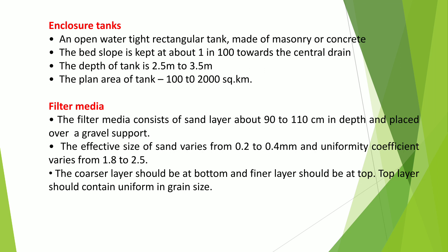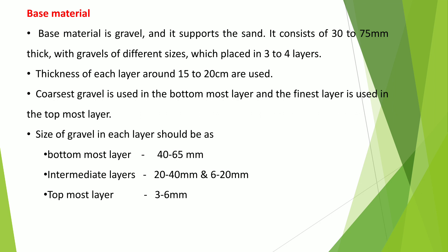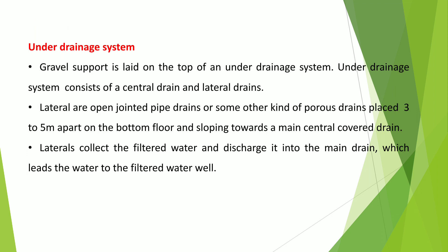The filter media consists of a sand layer about 90 to 110 cm in depth, placed over a gravel support. The effective size of the sand varies from 0.2 to 0.4 mm, and the uniformity coefficient varies from 1.8 to 2.5. The coarser layer should be at the bottom and the finest layer at the top, with the top containing uniform grain size.